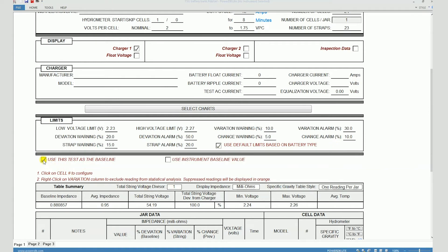When you do that, the baseline impedance will be calculated from the individual impedance values measured during that particular test. You also see a second checkbox appear here when you check the "use this test as baseline" option. By checking that box, you can transfer the baseline impedance value that you may have entered on the instrument while running the test on the battery string.